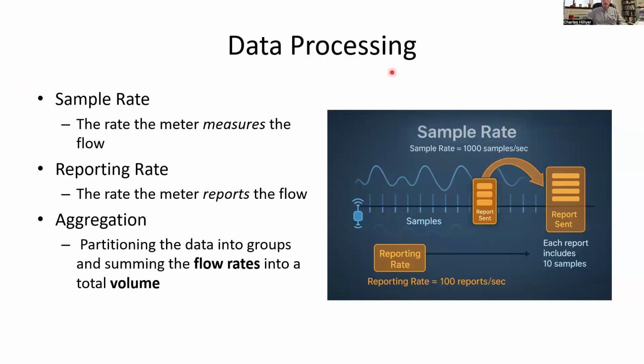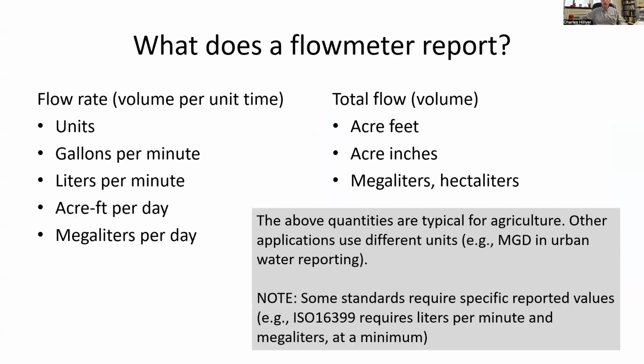Now, there's another important data processing step that we're going to talk about quite a bit more later, but it's important to remember that aggregation, which is where you're basically grouping the data and in most cases just adding it up. That aggregation step is a really important part of the process. Now, I talked about the reporting rate. What exactly does a meter report? Many of you have probably heard of flow meters and seen flow meter data, and you know flow meters report gallons per minute. But they don't all report gallons per minute, and many of them, especially the newer ones with more advanced electronics, report a lot of different things.